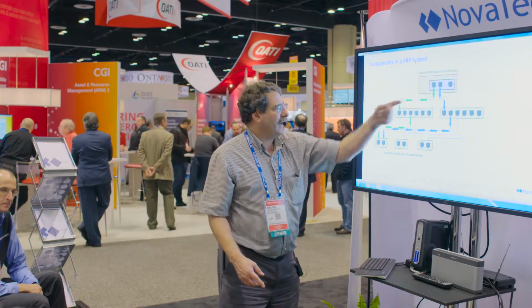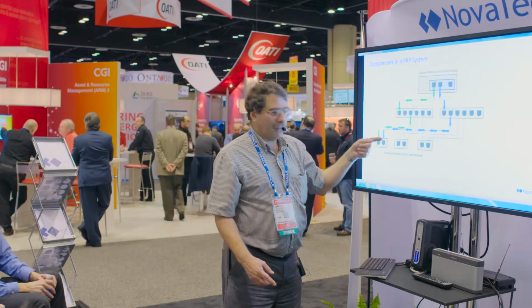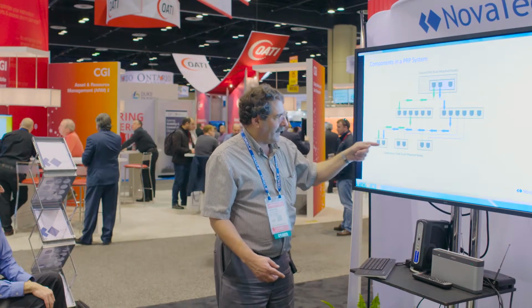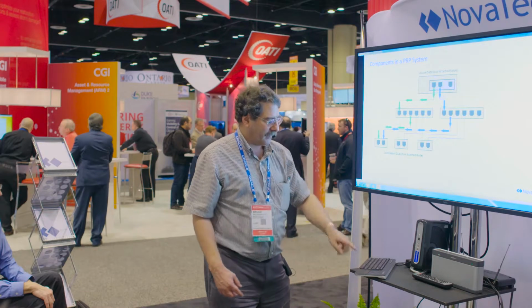For example, LAN A could win. If you break LAN A, then LAN B is going to be the first one in. The system doesn't care. The first one in there wins, and there's absolutely no packet loss at all. The key is that the receiver has to dump the redundant message, but it knows this by sequence numbers.